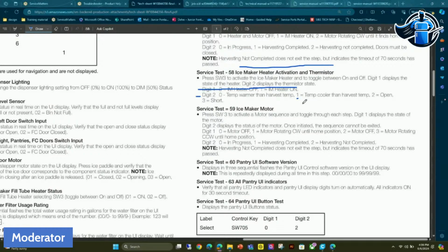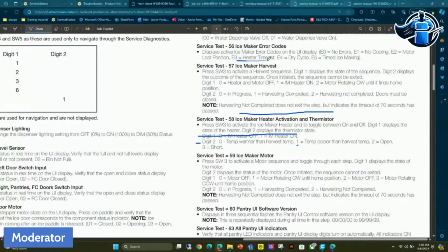The problem with test 58 is if you run test 57, our harvest test, it turns that heater on and heats up the compartment, and then you're going to generate a 00 on test 58. So it's important to check test 58 before you run a harvest test, to verify you're not having a temperature issue. That's just to prevent you from going down crazy rabbit holes you want to avoid.